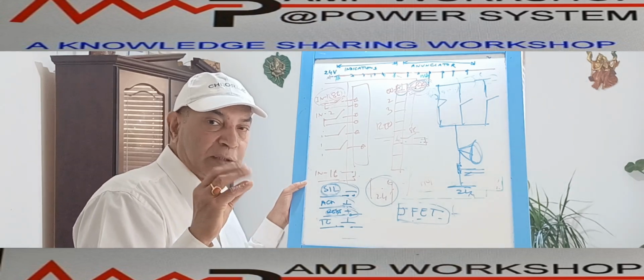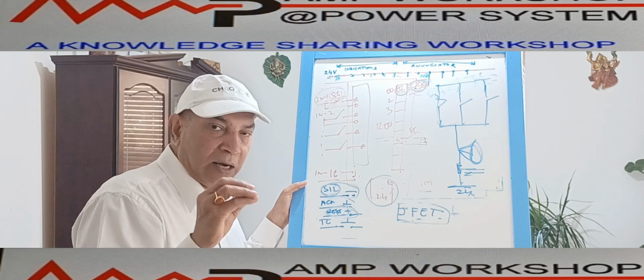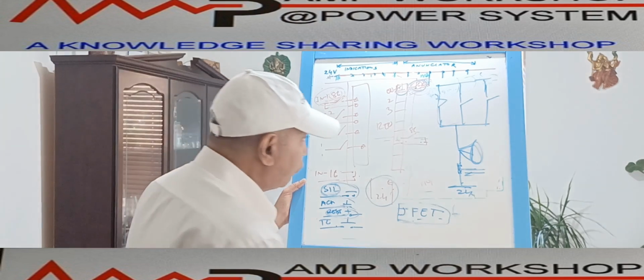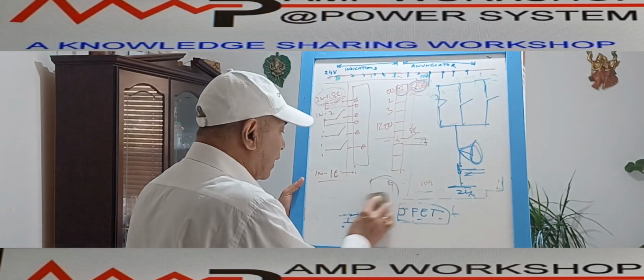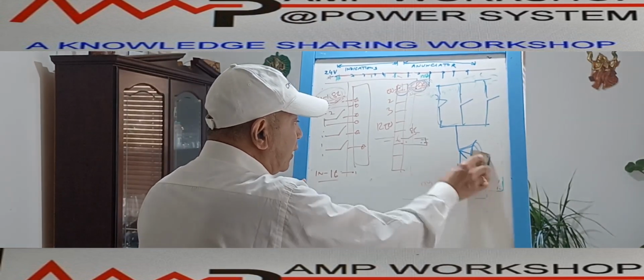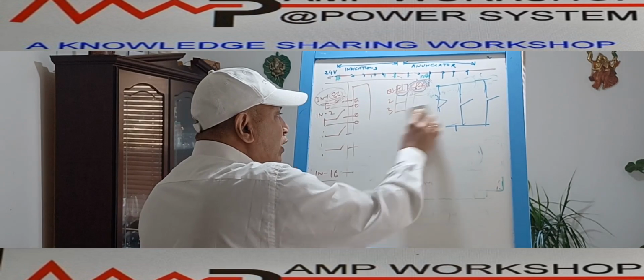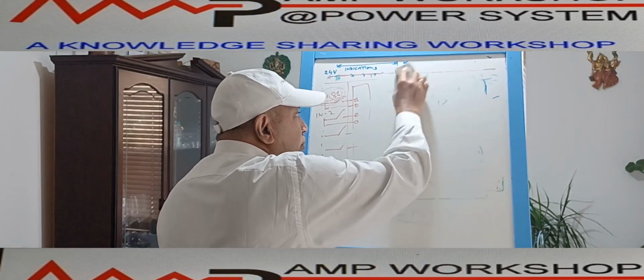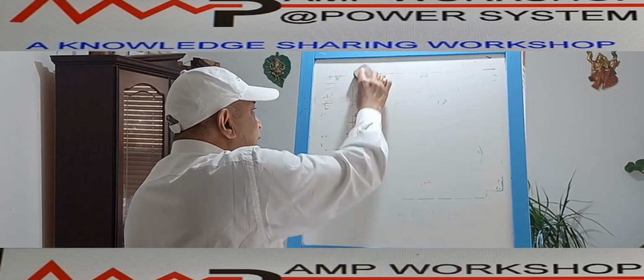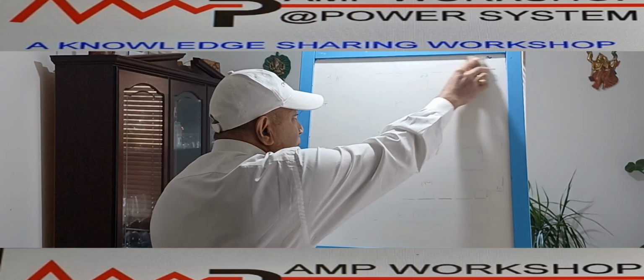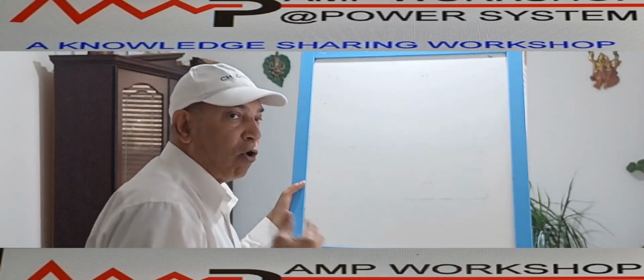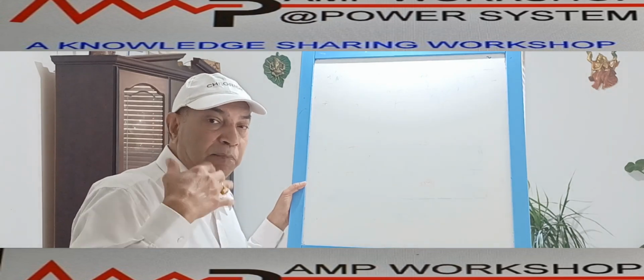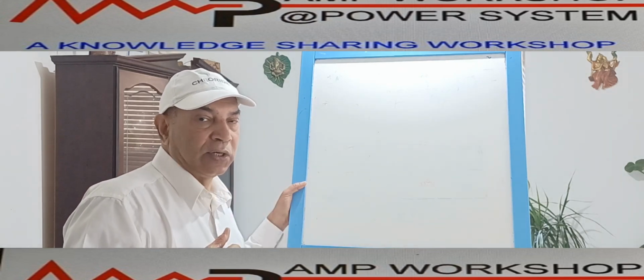Flashing will be very high speed and flashing will be slow speed. So why are we using this thing? The most advanced annunciator, we are providing all this facility to understand which protection has operated or which abnormal condition has come first to the electrical system. Because sometimes one fault or one abnormal condition can activate multiple abnormal functions. In that case, multiple lamps, suppose we have shown all these things.